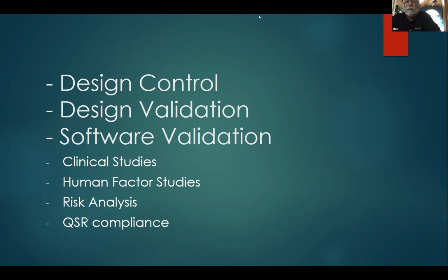Next thing is the design validation. Once you have your software, you've got to make sure that you validate the software to make sure that it's going to work clinically. And again, you have to have your indications for use to determine how you're going to validate that design. And then you want to make sure that the software is validated. It's very critical as part of your application that your device software has been validated. And I will go into that a little bit in the next few slides.